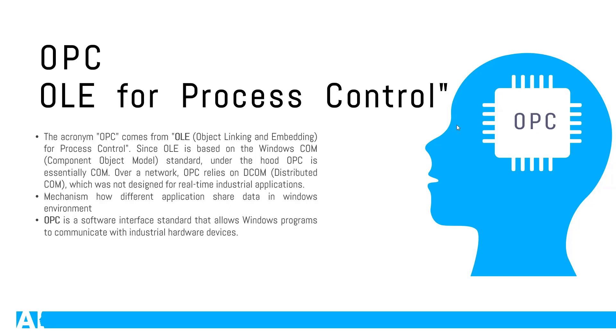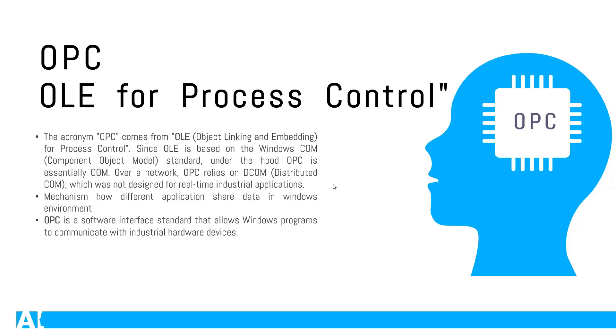If you talk further about it, OPC is essentially using COM if you talk about communication within the system. But if you talk about communication on a network, your OPC actually relies more on DCOM technology, which is distributed COM. This is a mechanism how different applications actually share the data in Windows environment.